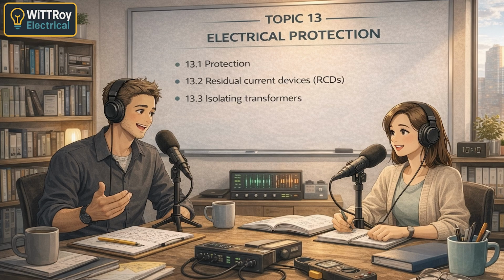So if more than 1 appliance is supplied, what must be done? They need to be earthed? Not quite. This is where students often get caught. Oh, okay. The exposed conductive parts must be bonded together. Bonded together but not earthed. Exactly. Bond together but do not connect to the installation earth. If you connect them to earth, you lose the isolation. Correct. That defeats the purpose of the isolating transformer. So bonding only, no earth connection. Yes, that wording is very examinable.